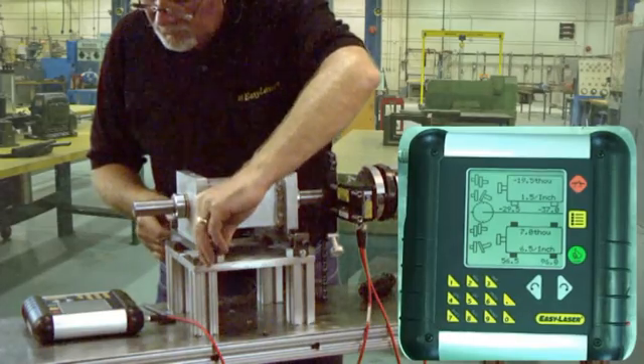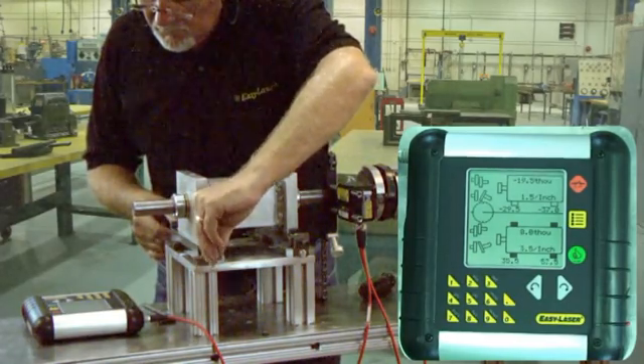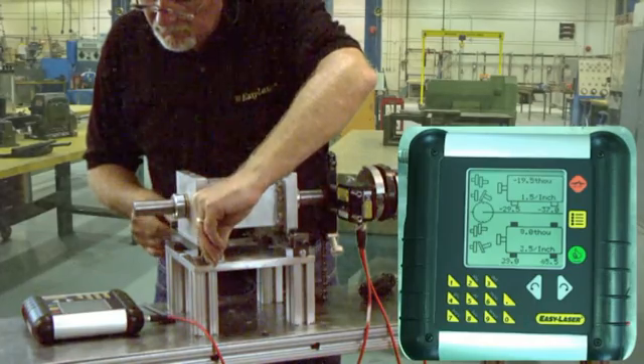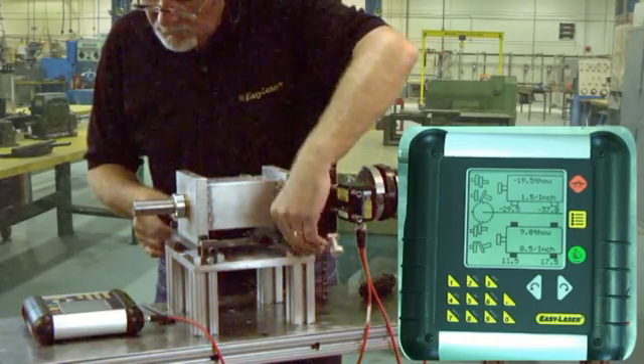To correct the horizontal misalignment you need to move the machine by the amount shown. You can see the values change in live time movement on the display as we correct the horizontal plane misalignment using the jacking bolts.